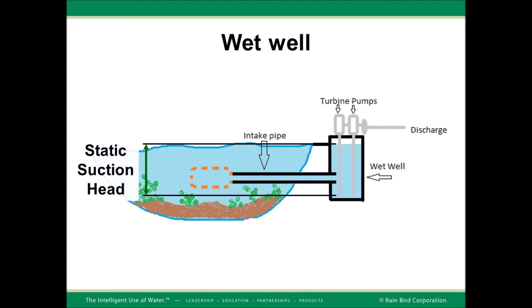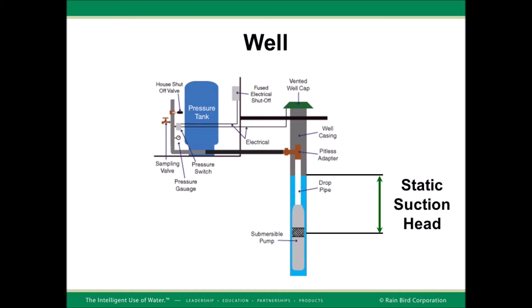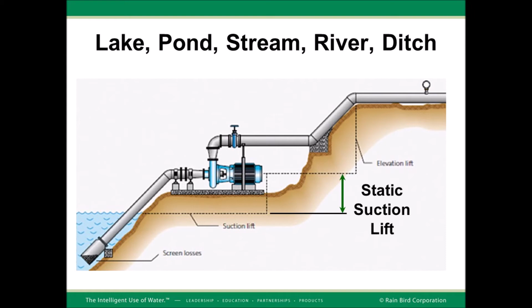This is another example of a suction lift condition where we are actually pulling the water from a well, like a borehole well or a deep well, for irrigation purposes. So we have pump stations which can operate in these conditions as well. Here is another example of a suction lift condition where the water for irrigation is pulled from a lake. So the pump station sits beside the lake, and then there are some strainers involved, and then we get the water pulled into the pump and pressurize it for the irrigation purposes.